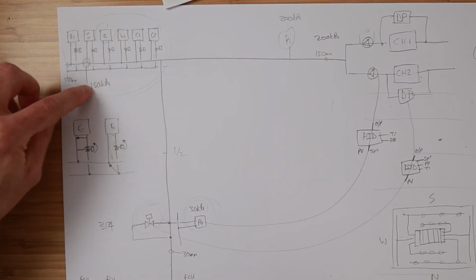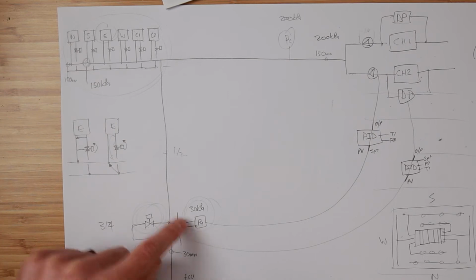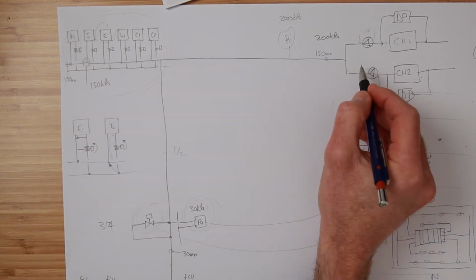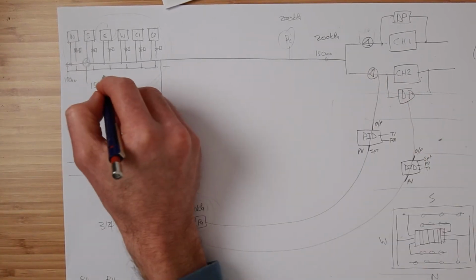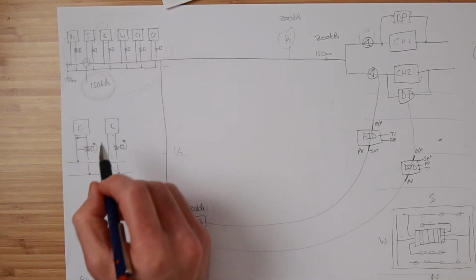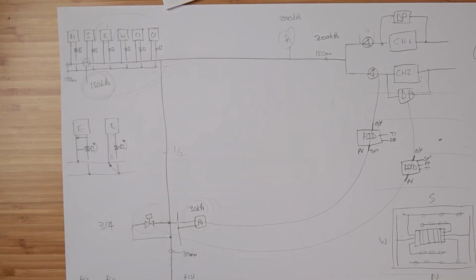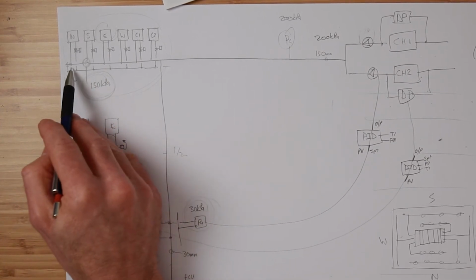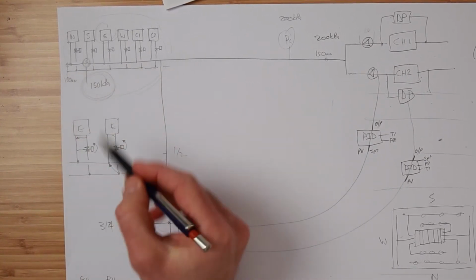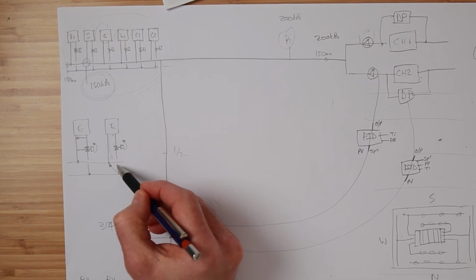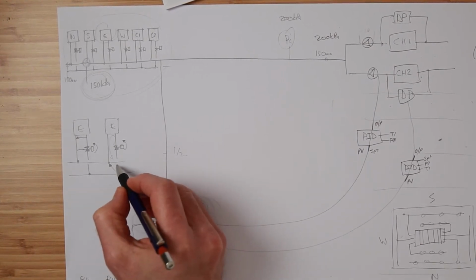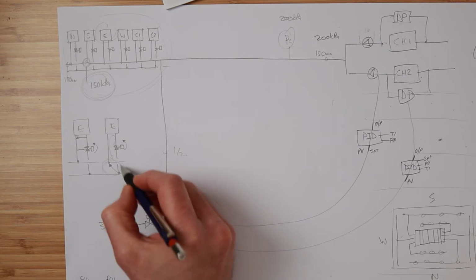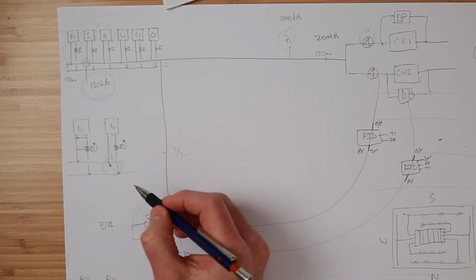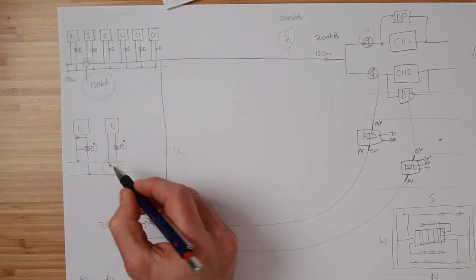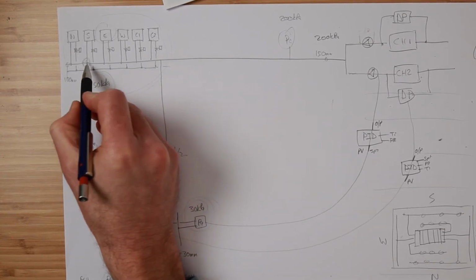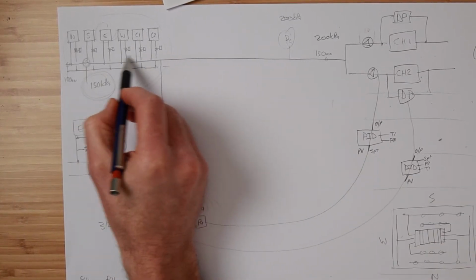So when they do water balancing and they give you that set point and you use that set point of 150 kPa here and not the 30 kPa here, it means that your pumps are always controlling to maintain the pressure correctly at the point where the load mostly is because of how you calculate valve authority. See here, if we can hold this pressure correct here, then we're holding the correct valve authority, although we don't know what the number actually is in real life. So again, if we hold the pressure here, we're sort of trying to get the pumps to hold this area here.